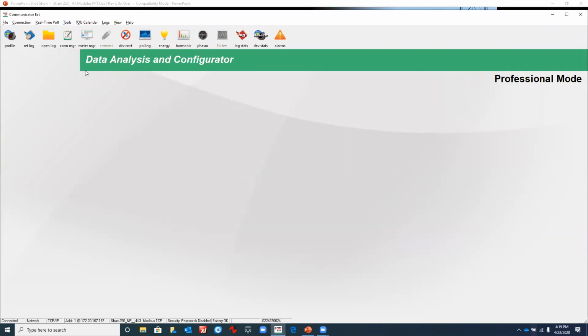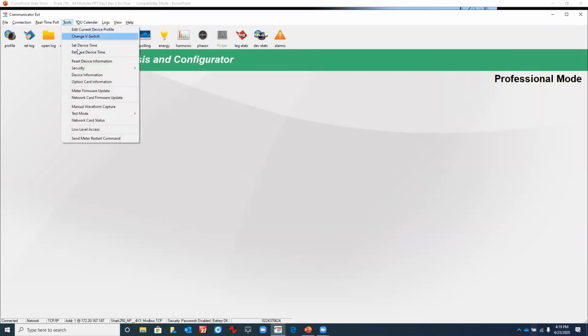The first part of this connection, I think we're going to talk about the V-Switch. So we'll go to the Tools screen and the V-Switch. The V-Switch basically gives you the option of installing certain keys that allow us to upgrade meter memory, additional memory for the extensive data logging, which we talked about a little bit earlier. The optional V-Switch keys range from V2 to V4. This also gives you the ability to look at additional trending, limit alarms, I/O changes, and other things such as waveforms. I think pretty much that's as far as the limitations of what we have.